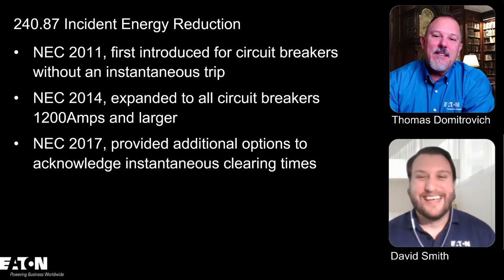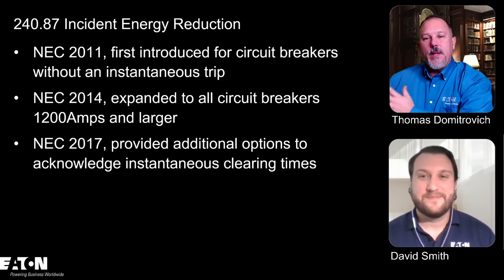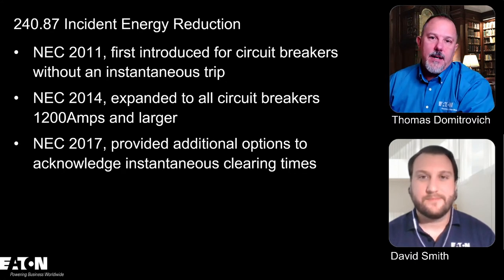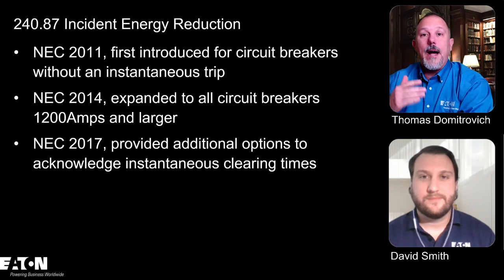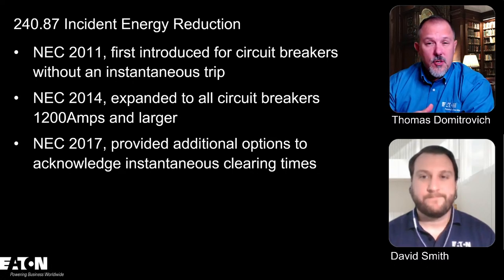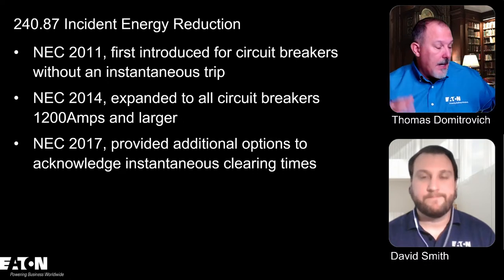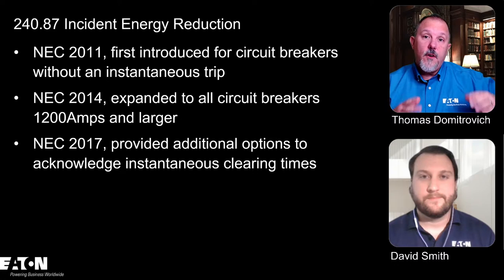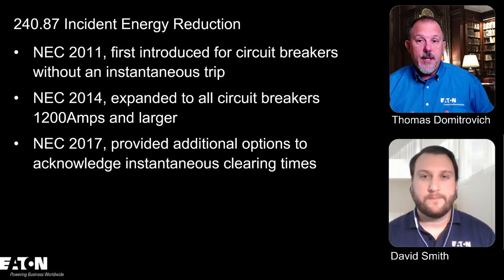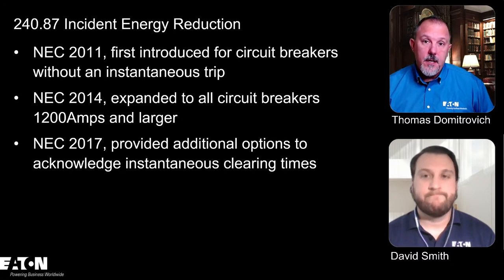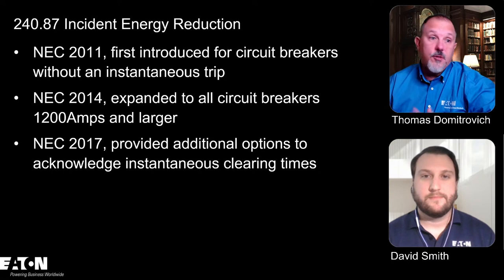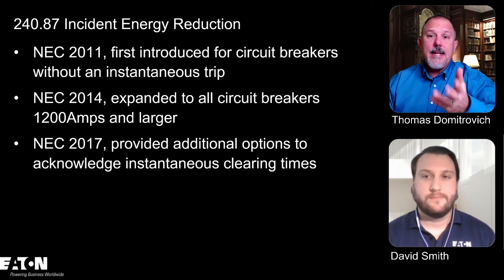So in the 2011 cycle, and we'll talk a little bit about the history as we get through, it was 2011. I call it pretty historical outside of ground fault protection of equipment, GFPE, that went in the National Electrical Code in 1971. GFPE went in 1971 in 230.95 to solve arc flash events at service entrance equipment. And it wasn't until 2011 that we saw another code change that actually requires the installation of arc reduction technologies to address the same, if not similar, issues that GFPE was trying to solve in the beginning. So it's had some history and it's changed over time.